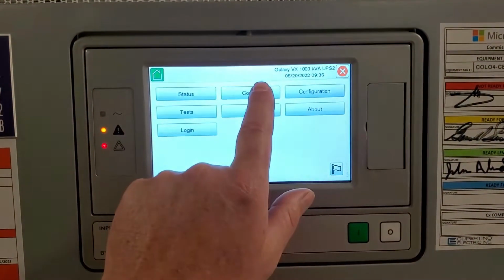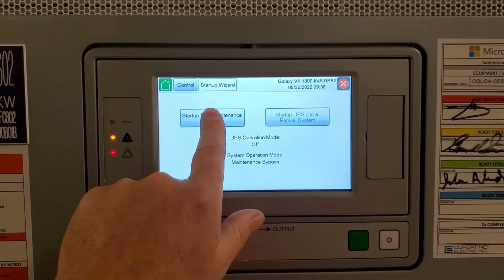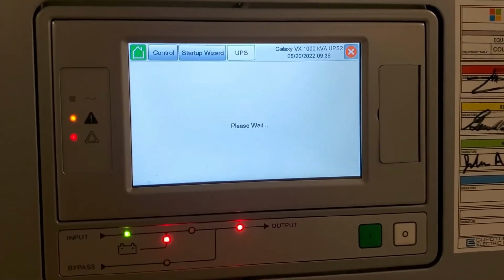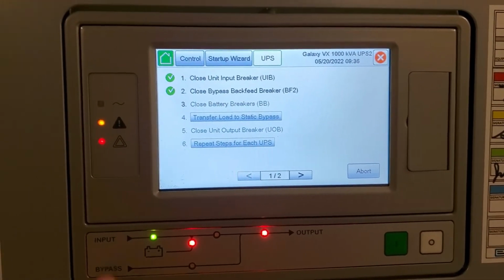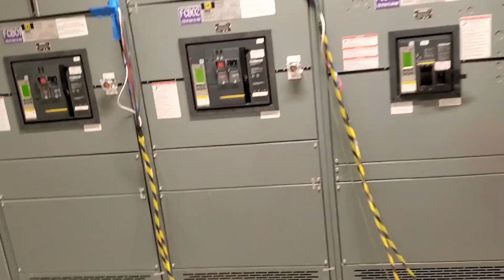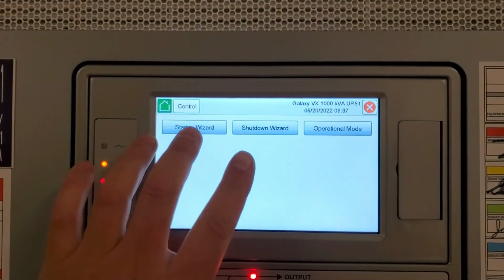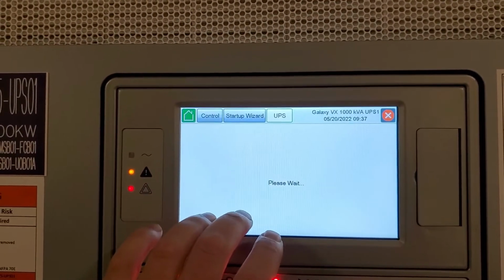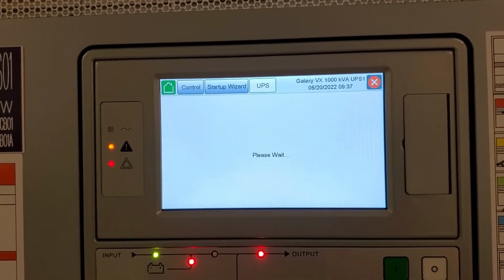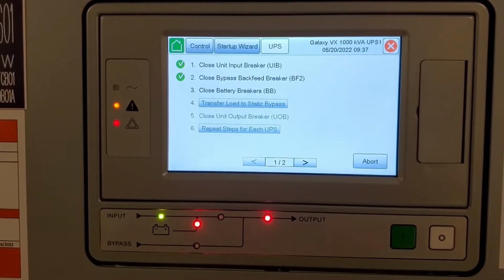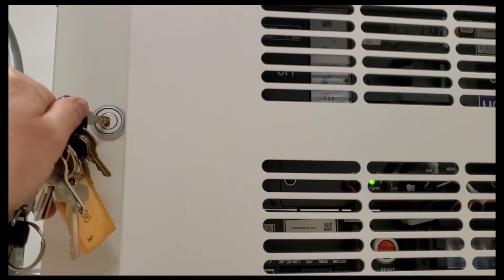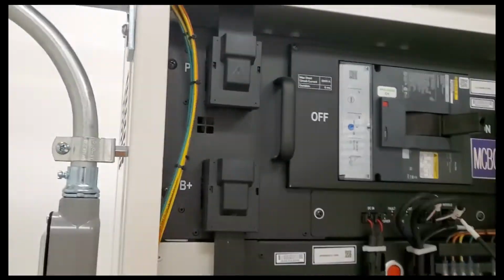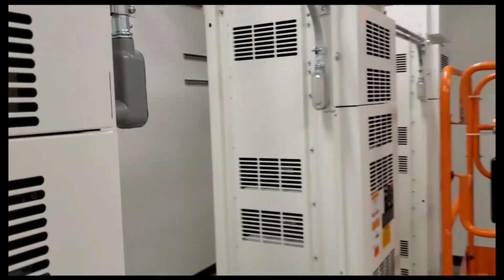Okay, right here I'm approaching the UPSs. I'm putting them into control, and I'm basically doing a startup. Right now I've just closed the input breakers. As you can see, both FCB 1 and 2 are closed. Both UPSs are energized. I'm doing a startup wizard, and I'm starting up from maintenance bypass, meaning that both UPSs were de-energized. Next step is to close the battery breakers. So I come over to the battery breakers, open up the door, and I close all 4 battery breakers on each UPS. And this is for both UPSs since they're a paralleling system.